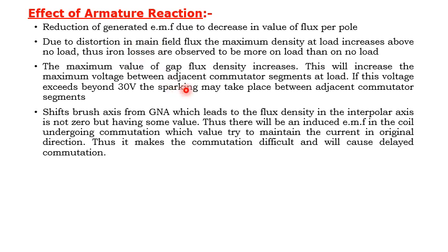Next, the maximum value of flux density increases, so this will lead to an increase in the maximum voltage between the adjacent commutator segments at load condition. If this voltage exceeds 30 volts, sparking may take place between adjacent commutator segments.